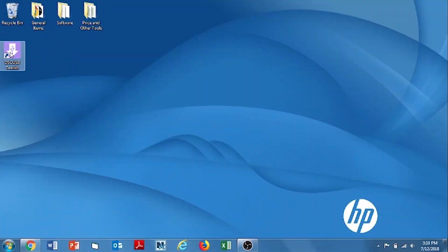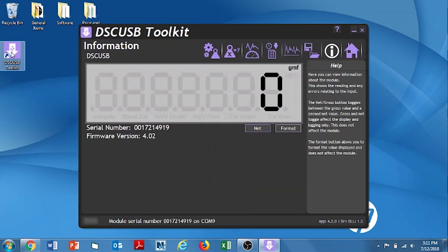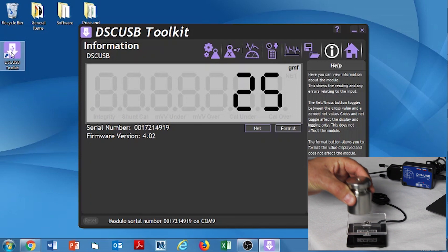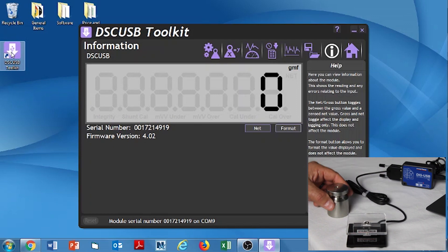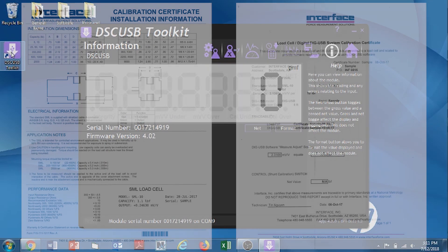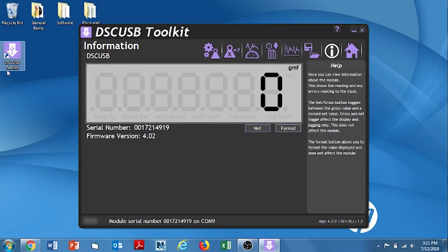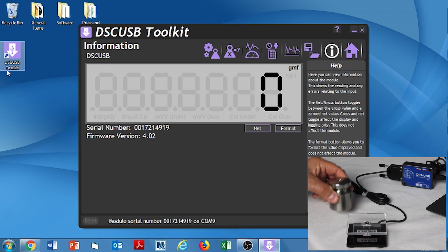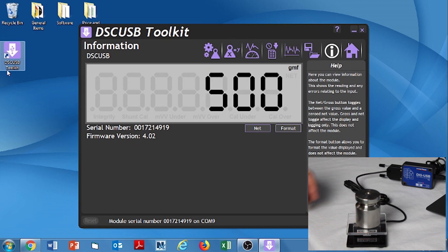Now we're going to open the DIG USB DSC USB Toolkit. And we're going to see the output. Now if your unit was purchased with an interface calibration, you should be able to do a quick check verify. And you will be verifying the calibration. And once you do that, you should be good to go. We're going to do that right now. So 500 gram weight or 1.1 pounds. And we're good to go.